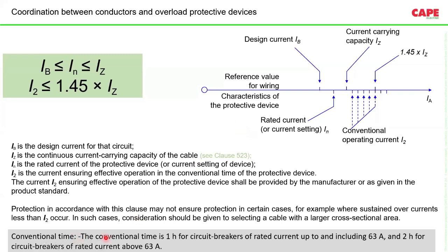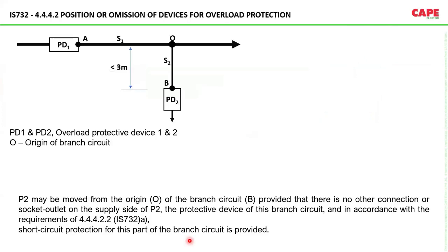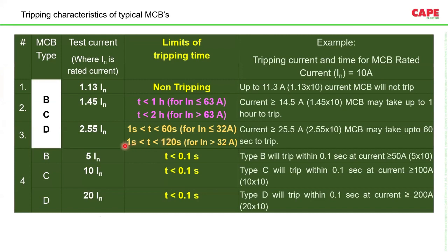Here you must understand that every protective device has a conventional disconnection time and a conventional disconnection current. Conventional disconnection time is up to 1 hour. Conventional disconnection current is 1.45 times. Similarly, the positioning of the device is very important. For example, I just put the tripping curves of MCB types B, C and D. For all three types, up to 1.13 times the nominal current, the device is not supposed to trip. Similarly, at 1.45 times IN, the disconnection time applies; this is called the conventional disconnection current.